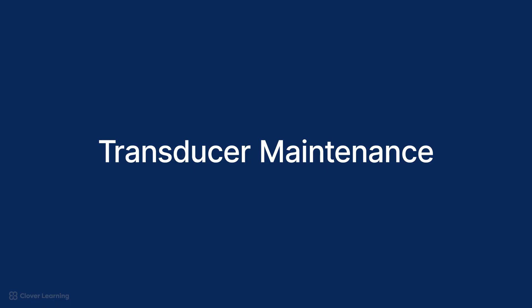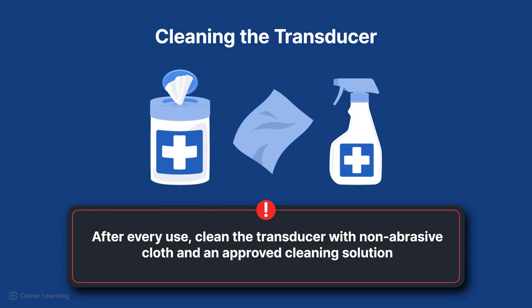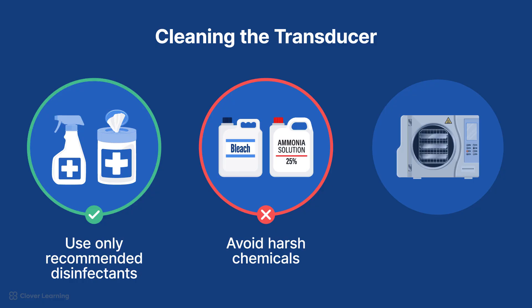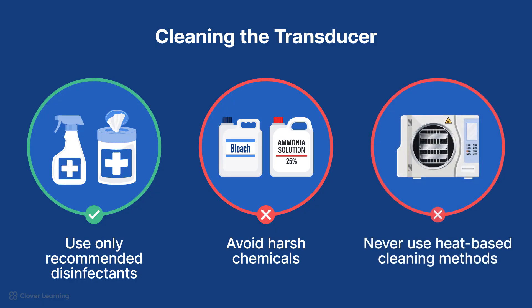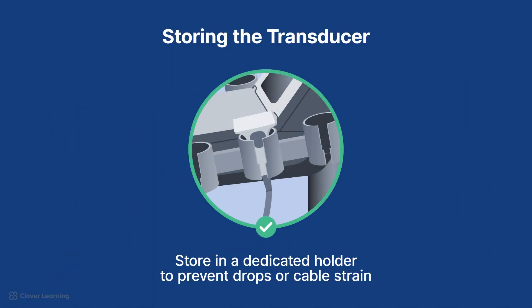Maintaining all of these components is essential for patient safety and proper operation of the transducer. After every use, the transducer should be cleaned with a non-abrasive cloth and an approved cleaning solution. It is important to use only manufacturer-recommended disinfectants, avoiding harsh chemicals that could damage the protective housing or crystal. Additionally, you should never use heat-based cleaning methods, such as an autoclave, for cleaning because it will damage the crystal and cause it to lose its piezoelectric properties. Finally, transducers should be stored in a dedicated holder to prevent accidental drops or cable strain.